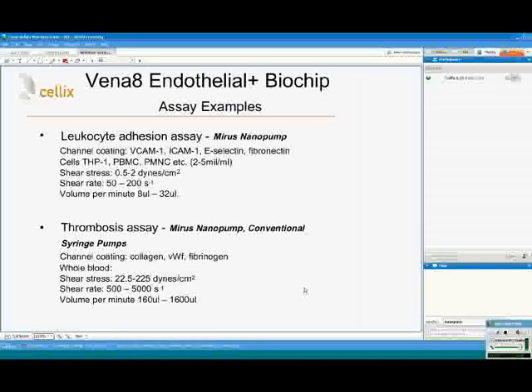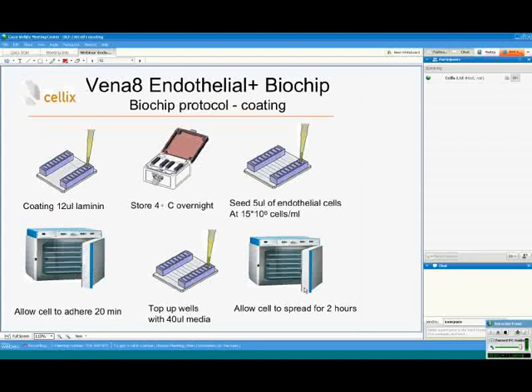I'll give you two examples of adhesion assays you can run on the Endothelial Plus biochips. The first is a leukocyte adhesion assay using the Mirus Nanopump. You can have different channel coatings and grow different endothelial cells. Cell types for leukocytes include THP1, PBMCs, or neutrophils. Typical shear stress is from 0.5 to 2 dynes per square centimeter, using 8 to 32 microliters per minute. For thrombosis assays, shear stress is much higher — from 22 to 220 dynes per square centimeter — with flow volume from 160 microliters to 1.6 milliliters per minute.